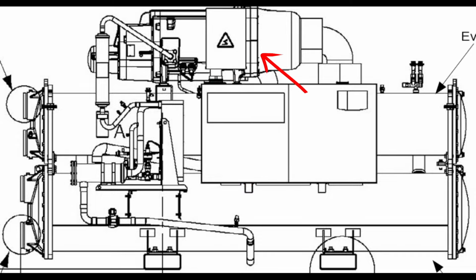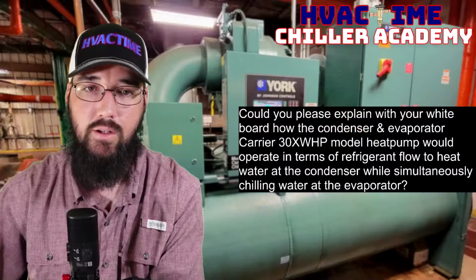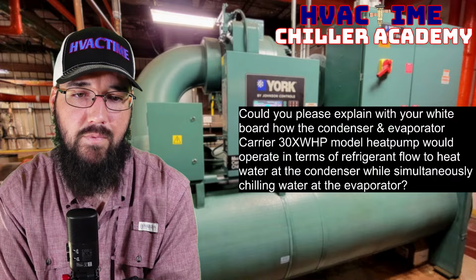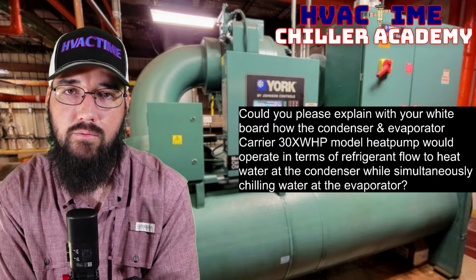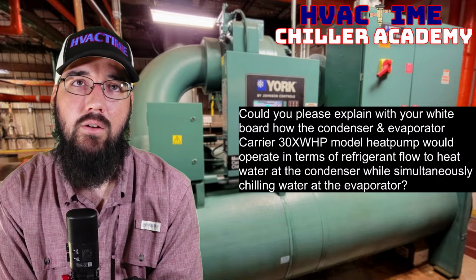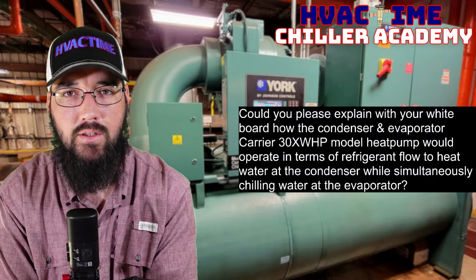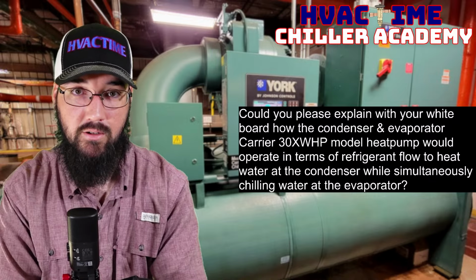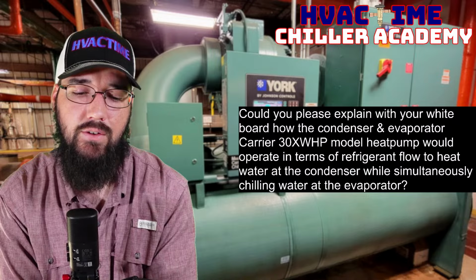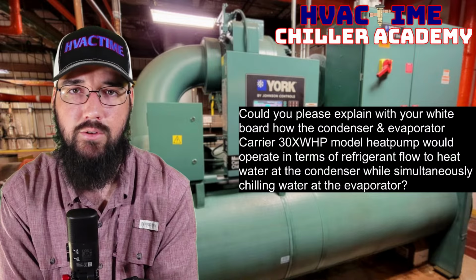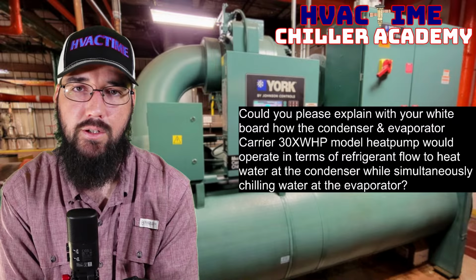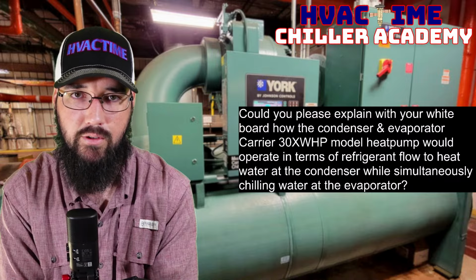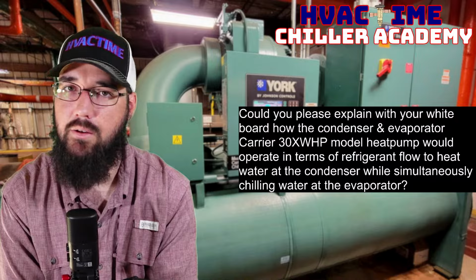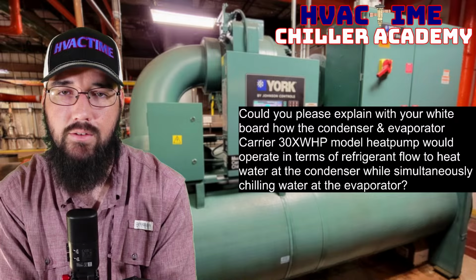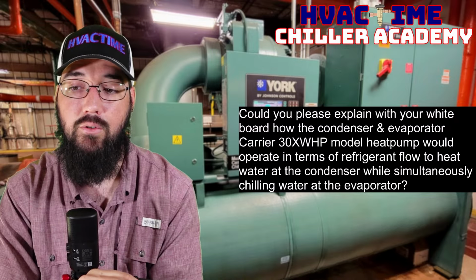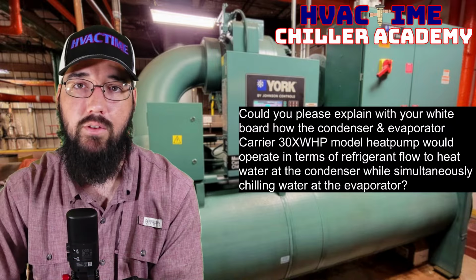Anyway, we're going to go based off of what we see this design being. And something that I want to point out here: some of these machines that are being developed and being called heat pumps, what they're designed to do, the evaporator and the condenser process, all of that remains relatively the same as on the chiller from a fundamental level. What is changing is the operating temperatures we're trying to achieve. With a normal chiller, we want to achieve a set leaving water set point of, say, 44, 45 degrees. And then our condenser water is going to be whatever it ends up being, 80 degrees. And this is water cooled, right? Condenser water, so 80 degrees or 90 degrees, whatever the case.